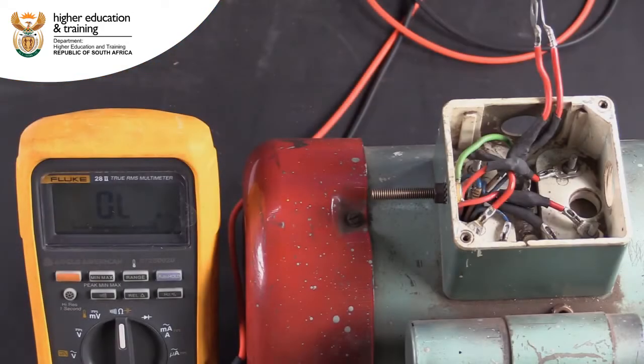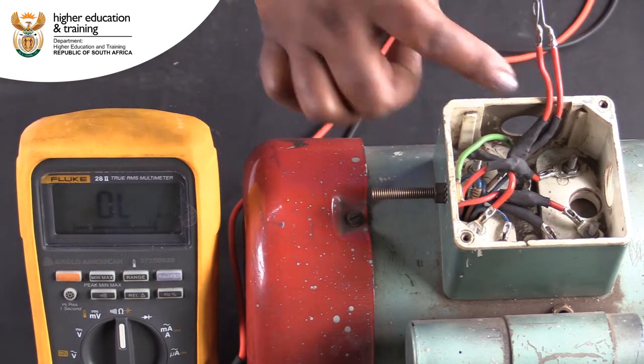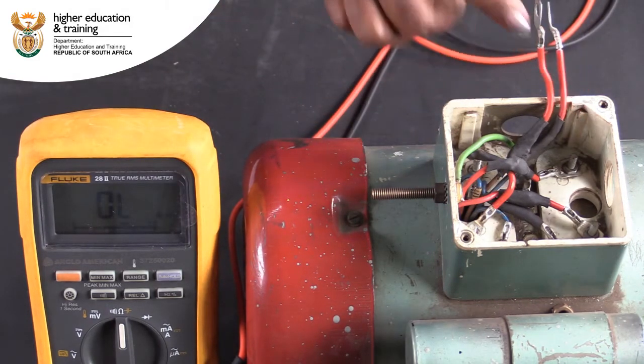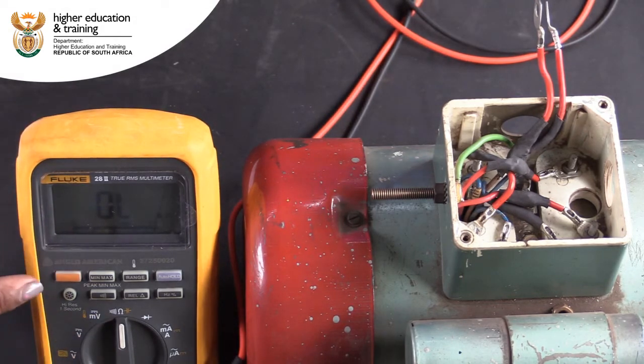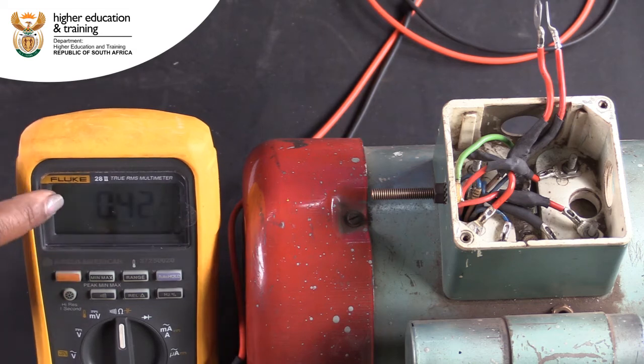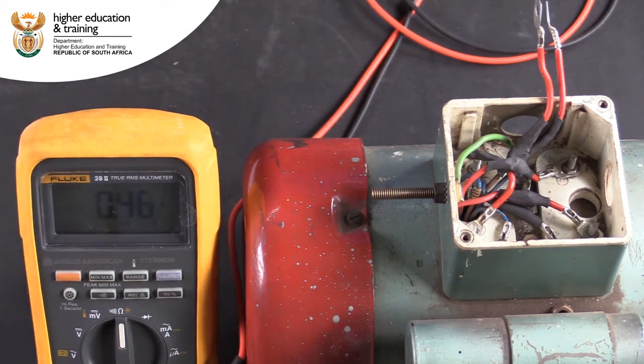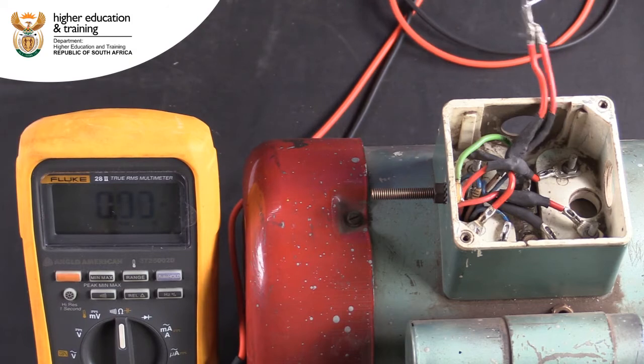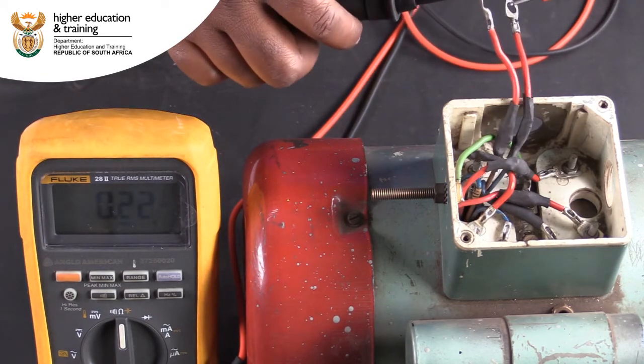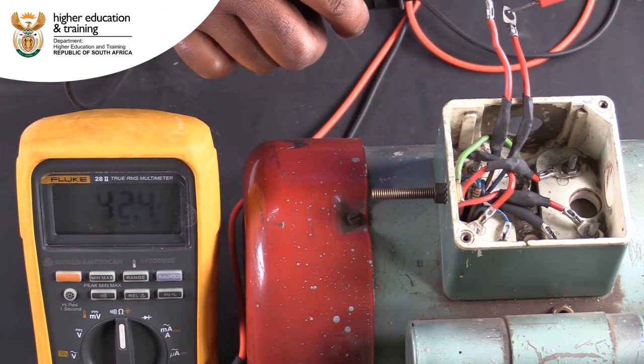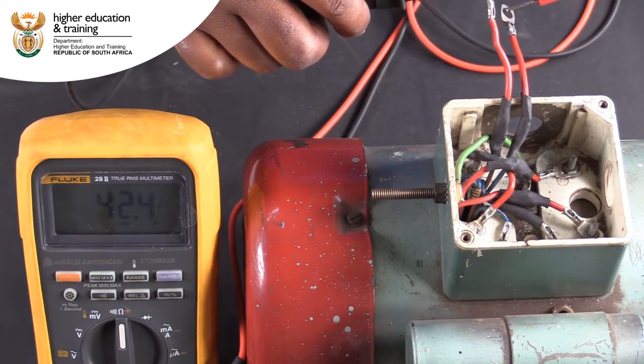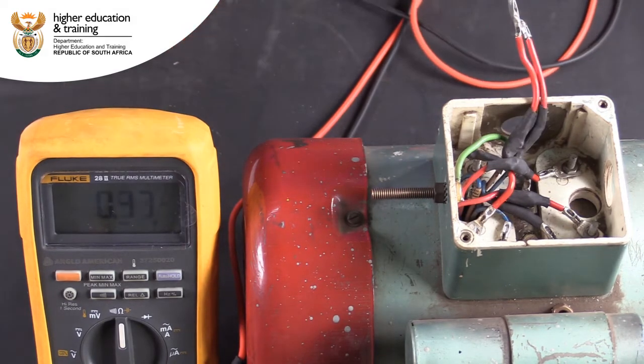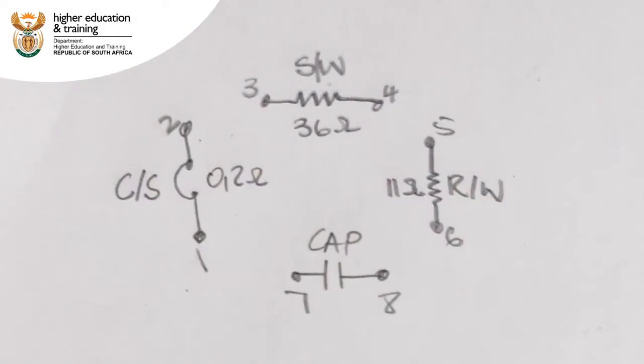The final two connections in our terminal box are presumably for the capacitor of this capacitor-start motor. To confirm this, we need to change our multimeter to the farad setting. When we connect the leads, we get a reading of 42.4 microfarads. Add the location of the capacitor to your diagram.